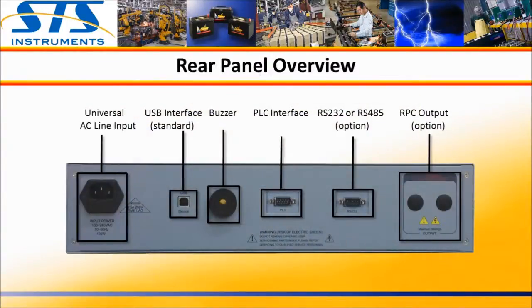Here is a view of the back of the 1656 tester. From left to right, we find the universal AC line port input, a standard USB interface, a buzzer that sounds when a fail condition occurs, an optional RS-232 or RS-485 serial interface, and the PLC interface. For automated test applications, a rear panel connector or RPC option is available, which allows test leads to be connected at the rear panel. This is shown on the far right.